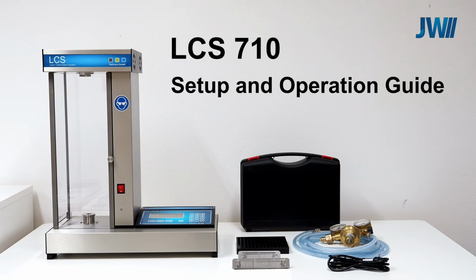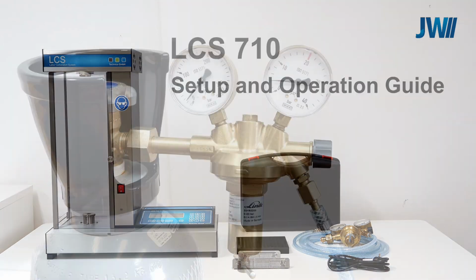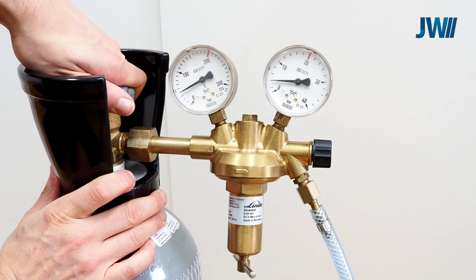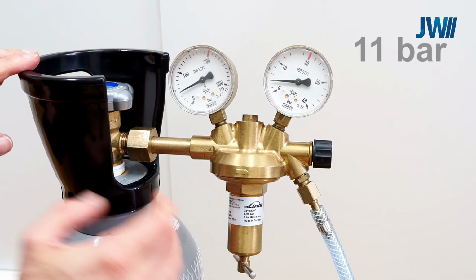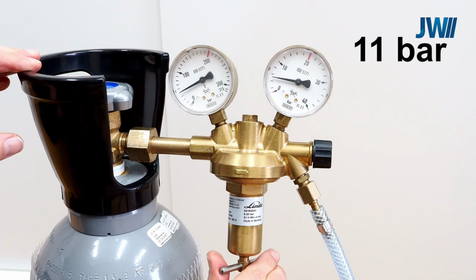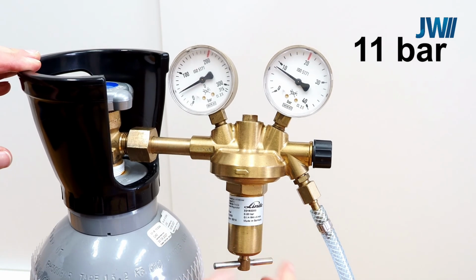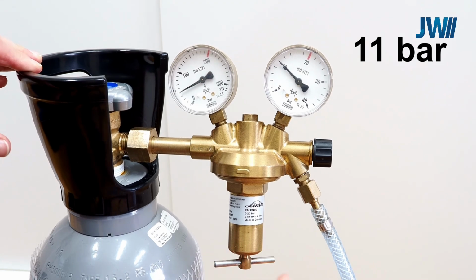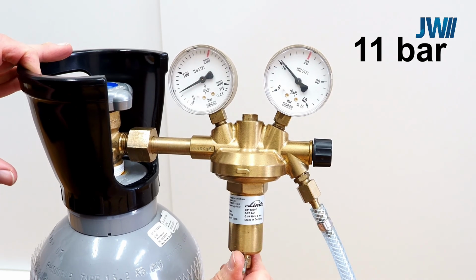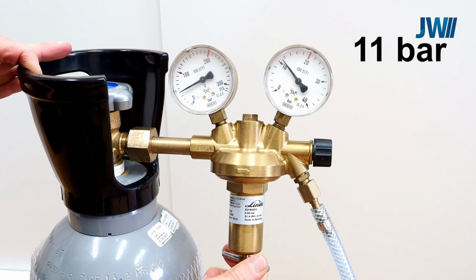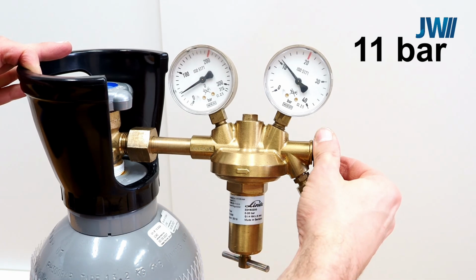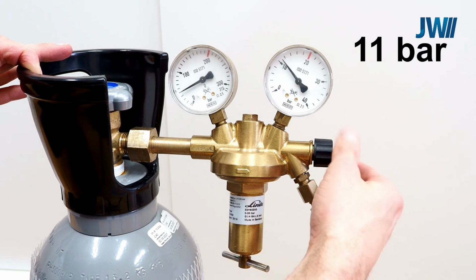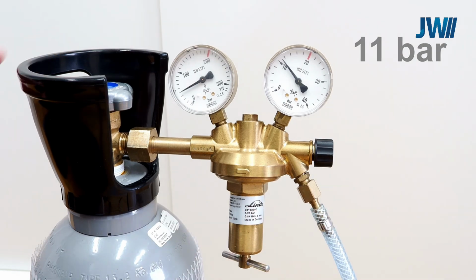In this video, we will show you how to set up your LCS. Here you can see the standard delivery contents of the LCS. Let's start with the CO2 supply. A pressure regulator is included. Open the CO2 bottle and adjust the pressure to 11 bar using the adjustment screw. Some pressure regulators also have an additional shutoff valve, which must be opened as well.